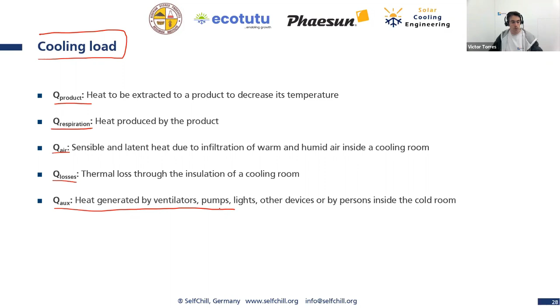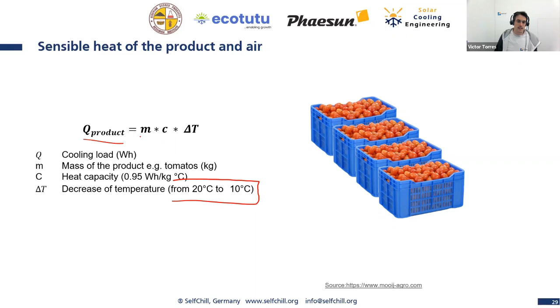The first one is the sensible heat of the product - we want to cool it down. As we said before, we want to know how much energy we need to cool down 500 kg of tomatoes from 20 degrees to 10 degrees, for example. That will be a case in our sample: tomatoes outside at 20 degrees, and we want to put them inside the cold room to cool them from 20 to 10 degrees. So we have the Q product, with the mass being 500 kg.